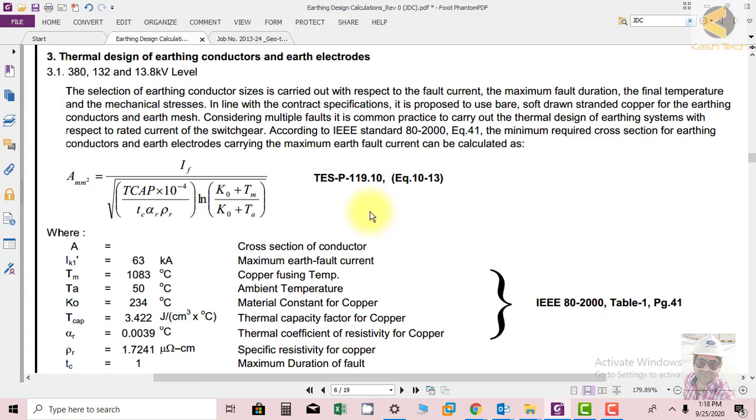rated current of switchgear. This is the practice we are following here: carrying out thermal design with respect to rated current of switchgear.